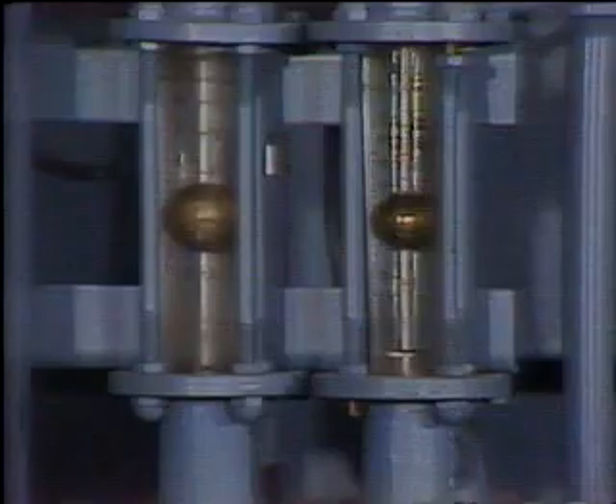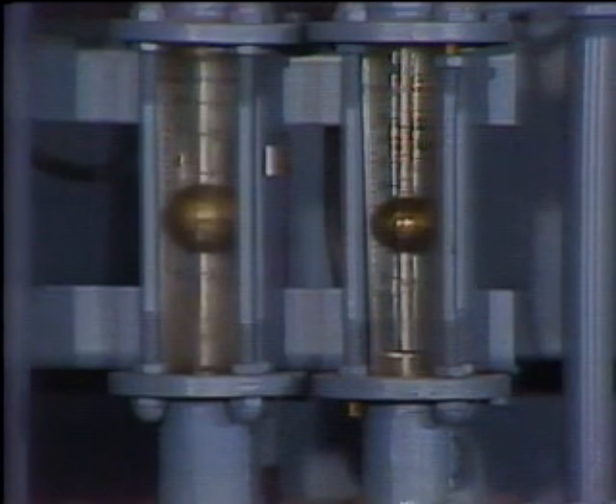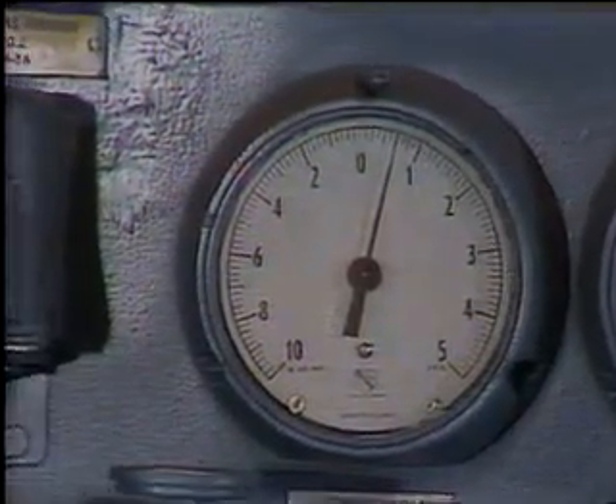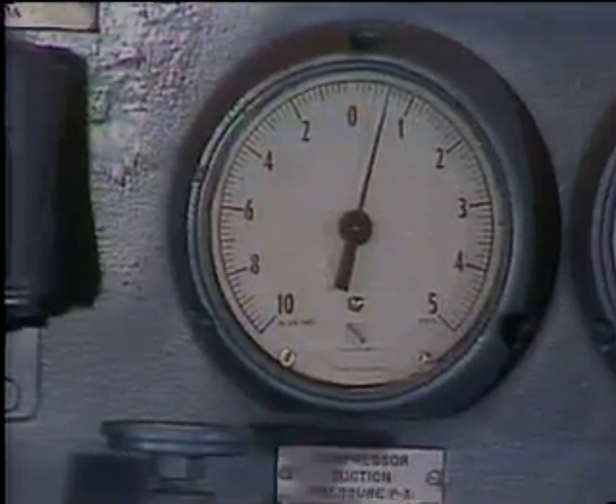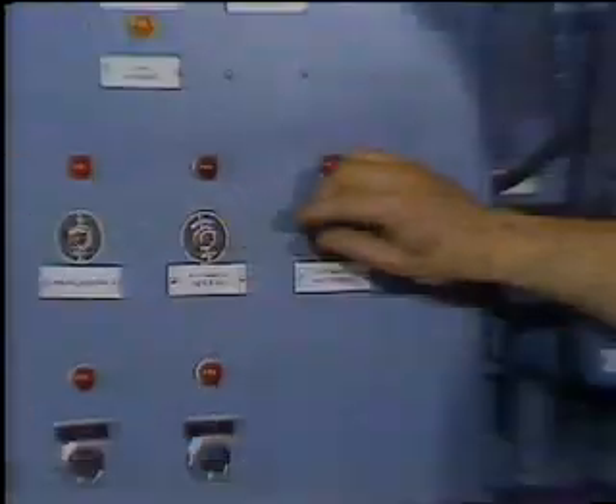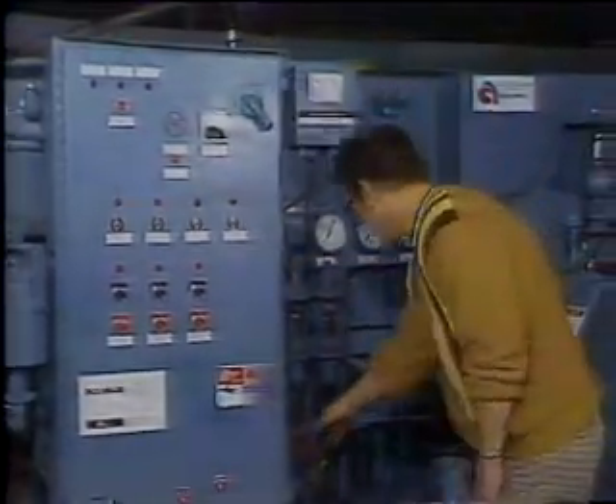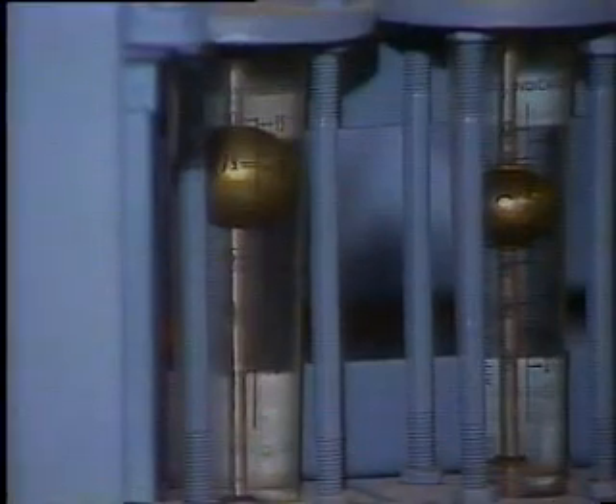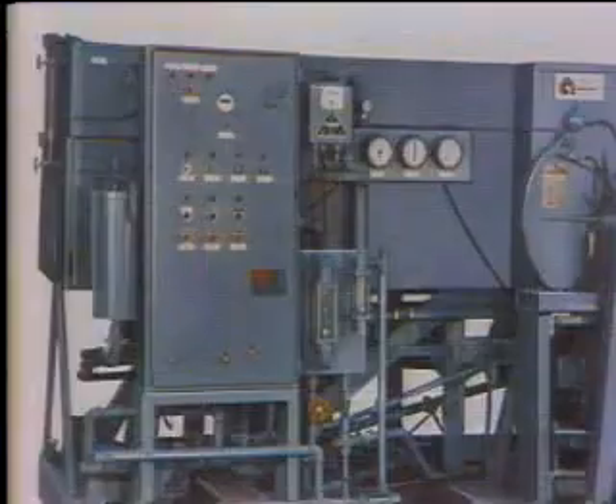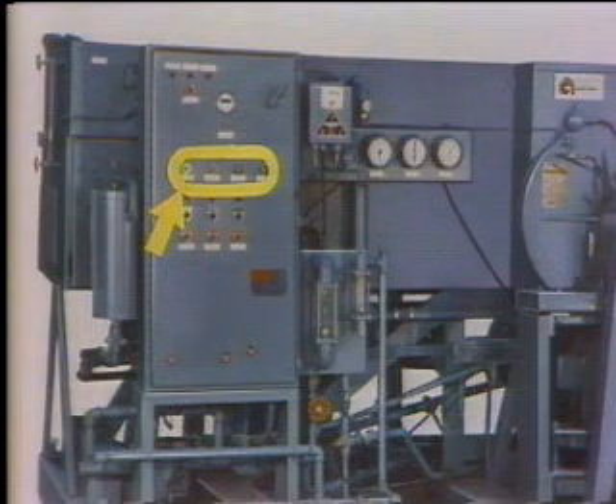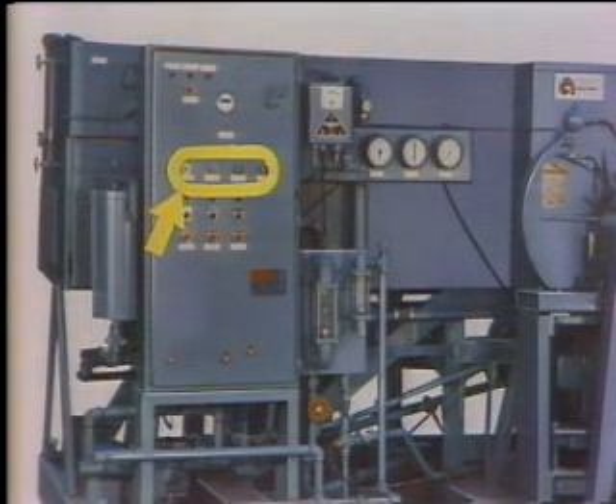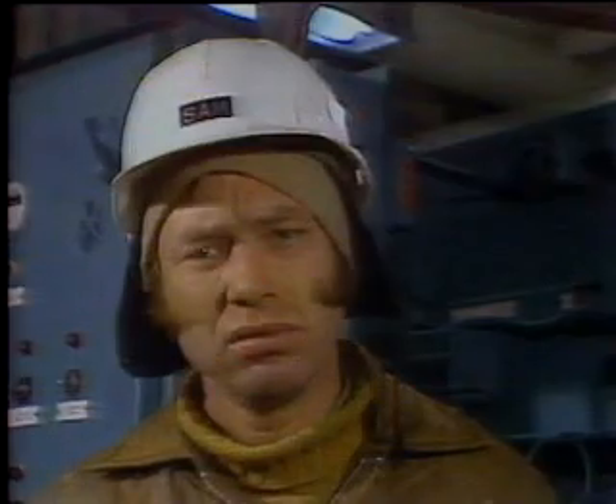Once the unit is producing distillate, check the compressor suction pressure. If it's maintaining its 0.5 to 1.0 psig pressure, turn the automatic heater to auto and leave one manual heater on. It should continue to maintain the pressure. If it drops and the unit is equipped with 2 manual heaters, go ahead and run the unit with both manual heaters on. This might have something to do with your problem, Sam.